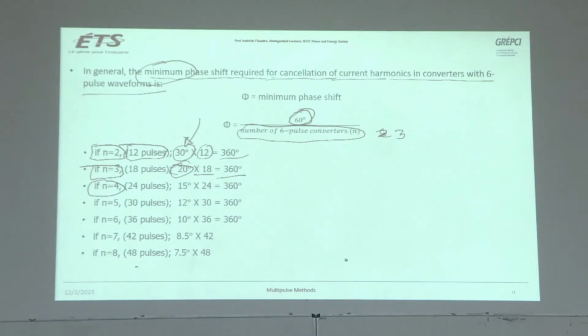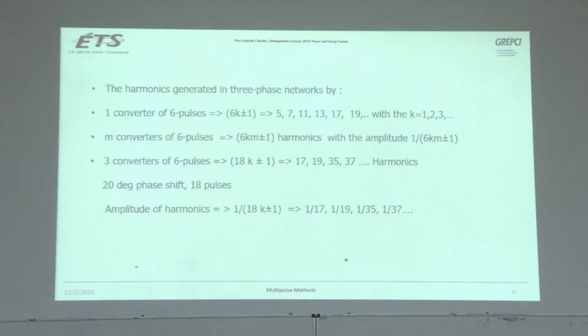If you have 4 converters, 24 pulses, then dividing by 4 gives you a 15-degree phase shift, multiplied by 24 pulses, 360. If you have 5, then 60 divided by 5 is 12 degrees. If you have 6, then it is a 10-degree phase shift and 36 pulses. So this is how you decide what your objective is, right?